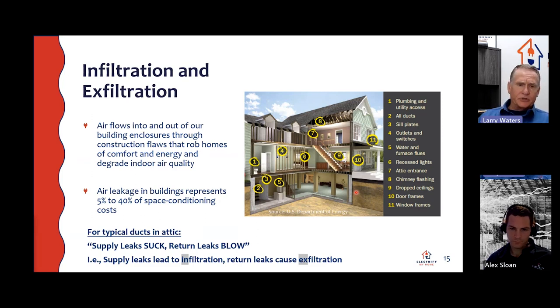These are the driving forces that move air. This is that law of thermodynamics that if you leak something out over there, it's got to come in from somewhere else. So air flows in and out of our building enclosures through different kinds of construction flaws. A lot of times it's flue pipes. The air leakage in the building represents 5 to 40% of the space conditioning costs. When we do load calculations, we can actually see how much the infiltration is causing on our system loads. And then a lot of this is going to be driven because of ductwork changes in the house as well.